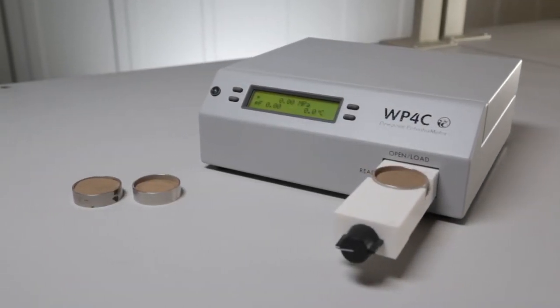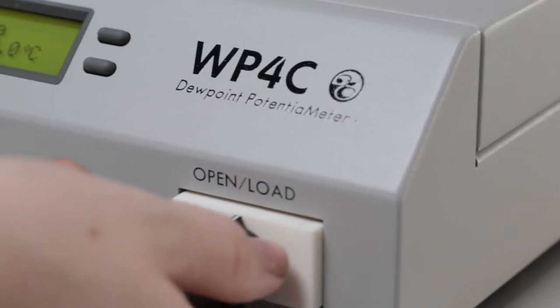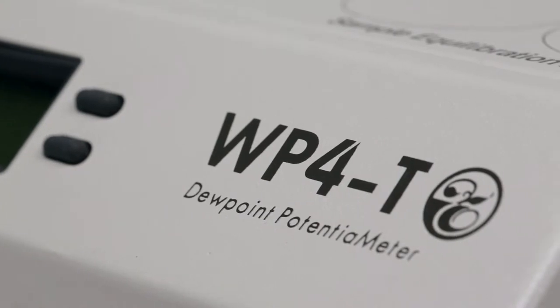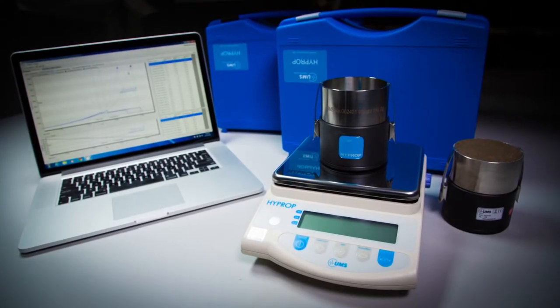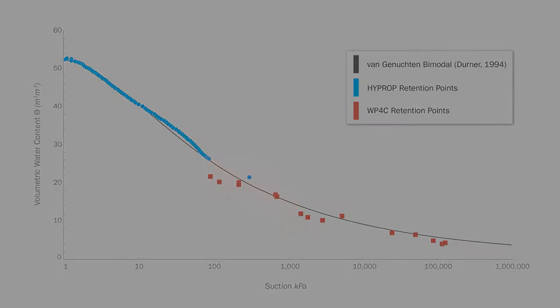On the outside, the WP4C looks like its predecessor, the WP4T, but inside it's a whole different story. The old WP4T could get up into the minus 0.5 to minus 1 megapascal range with fairly good accuracy. You can get down to the minus 0.1 megapascal range with the tensiometer-based HYPROP, but that left a hole in the range where so much interesting plant-related stuff happens. We were determined to make the WP4C capable of making accurate water potential measurements in this zone.